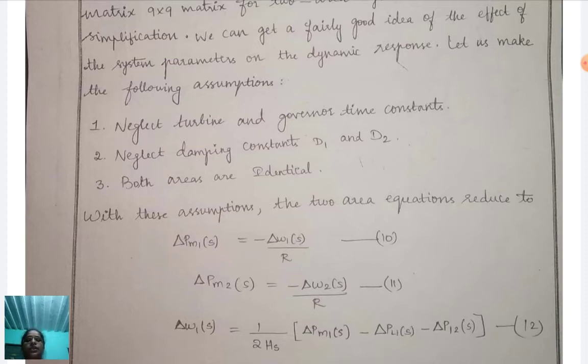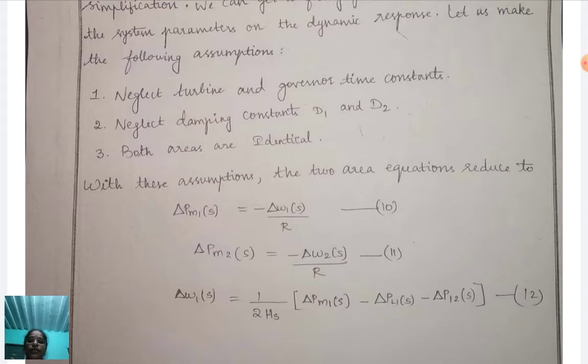With these assumptions, the two-area equations reduce to: del P_M1(s) = −del ω1(s) / R, and del P_M2(s) = −del ω2(s) / R. Therefore, del ω1(s) = (1 / 2Hs) × [del P_M1(s) − del P_L1(s) − del P_12(s)].